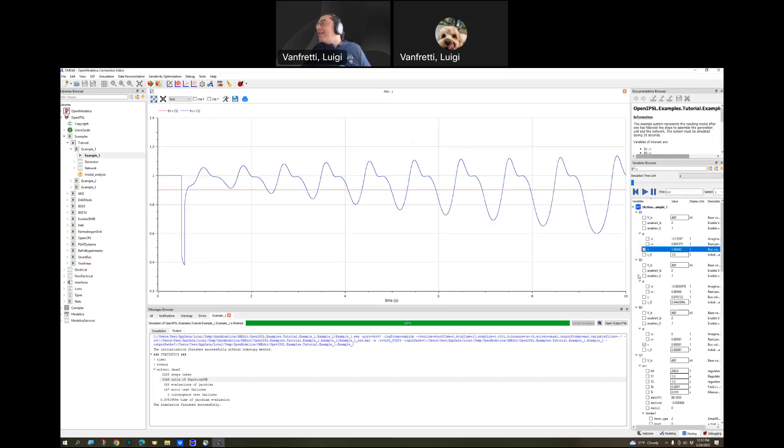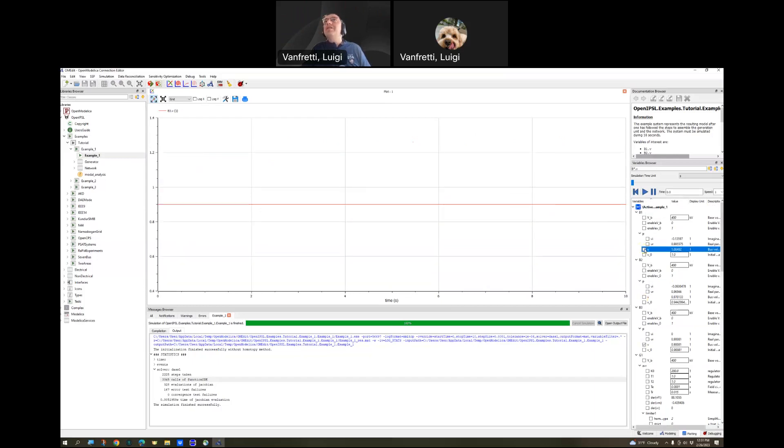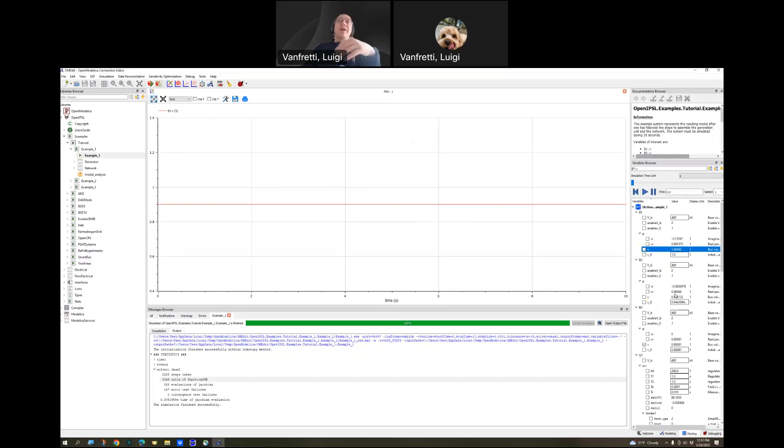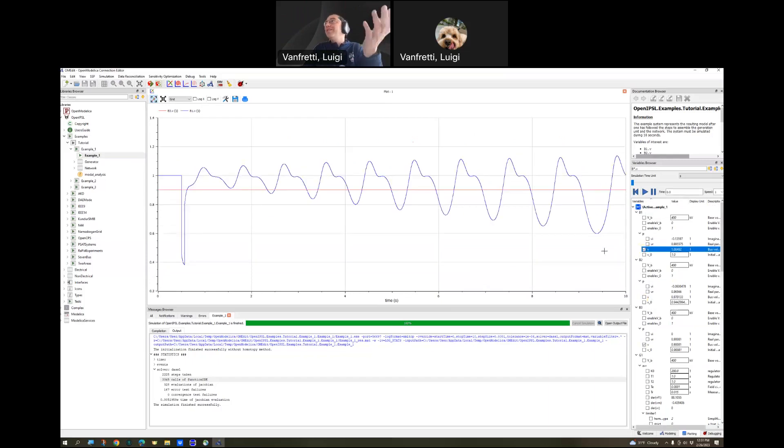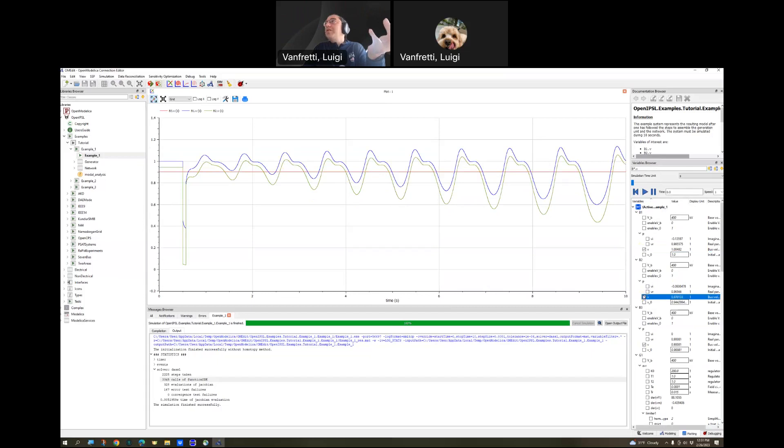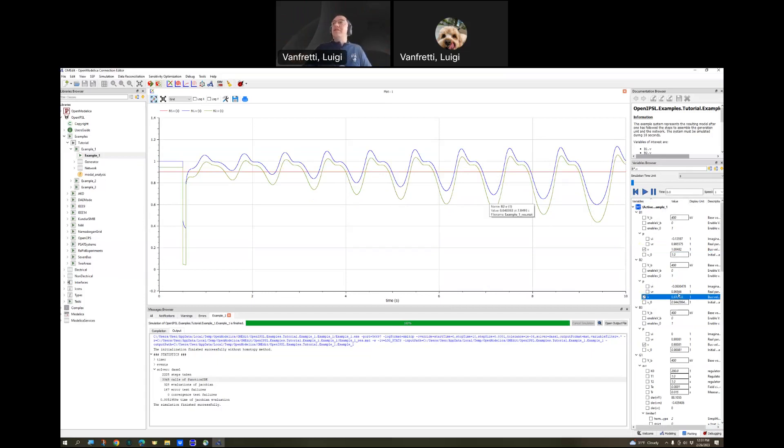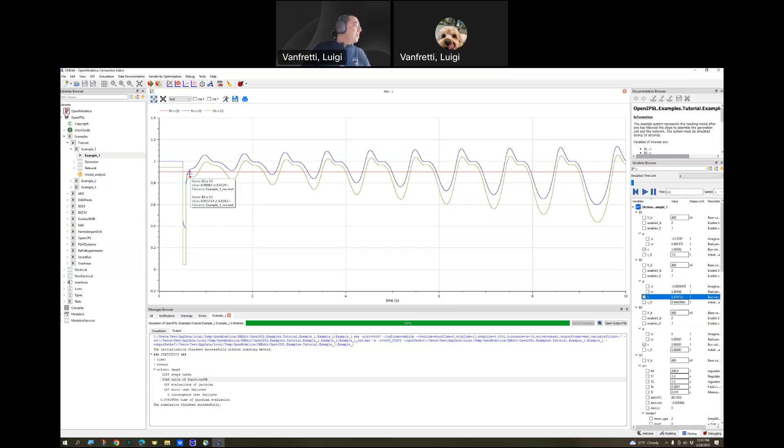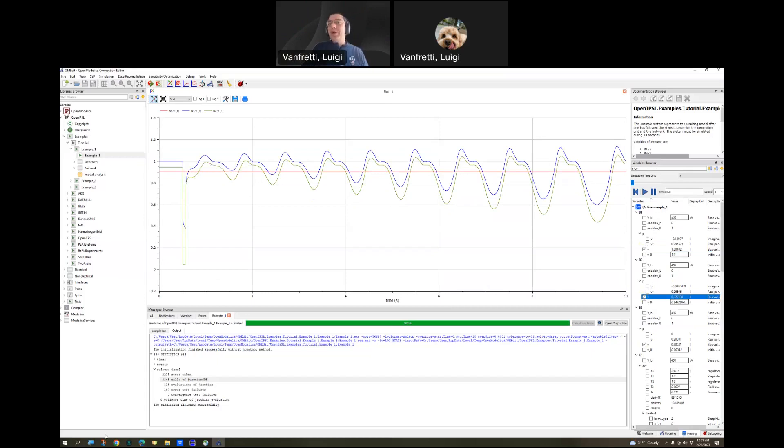Let me start from scratch because I'm not seeing so well with my old eyes. Bus three, it should be flat because the network is strong and it's going to survive. And bus one should be going nuts, because that's where the generator is connected. It's not able to stay in synchronism with the system. And where is bus two? Bus two is here. You can also see the oscillations being reflected there. This is a typical exercise that we do with electrical engineers that are still in electrical power.